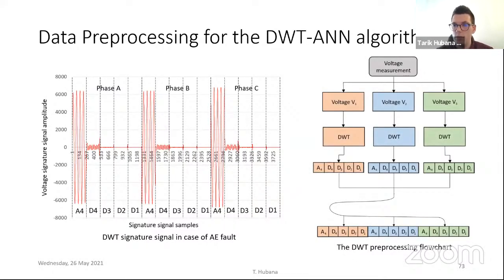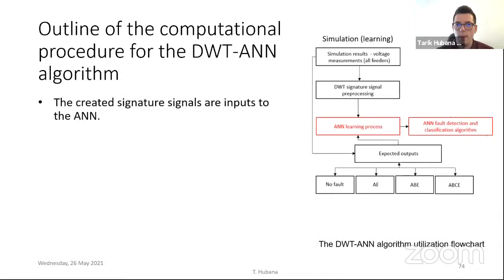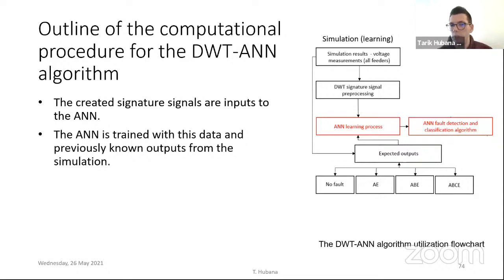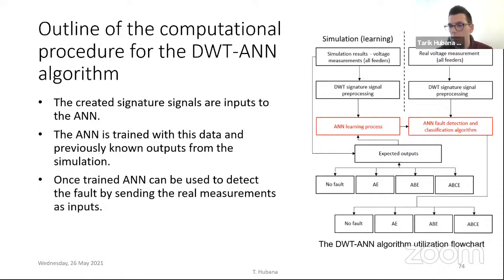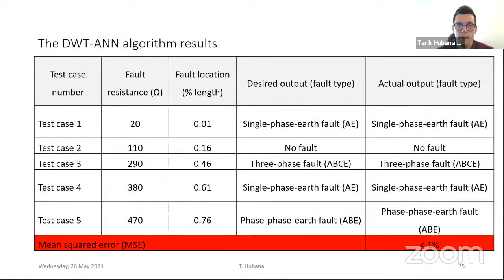On the right side, you see the methodology. So again, the voltages were measured, pre-processed with DWT. 5 different approximations and details were obtained, and these signals were actually glued together, concatenated together in order to have this signature signal. So again, the created signals are inputs to the neural networks. The neural network is trained with the previously known outputs from the simulation, and once trained, the network can be used in the same manner as the previous one to detect the fault and classify different fault types. Again, with the 5 different test scenarios, we see that the accuracy is great because the mean squared error is again less than 1%.